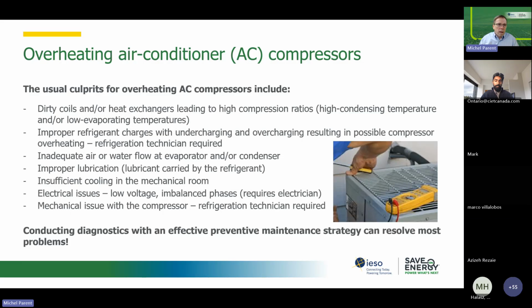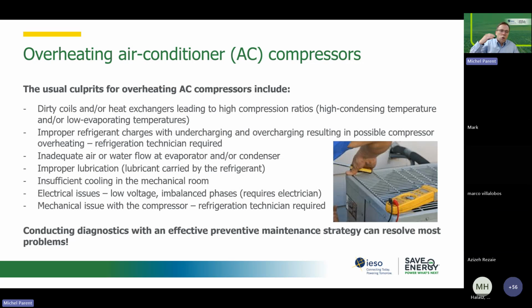If you've got ACs, air conditioners that are not a chiller, we're talking more about the type of rooftop unit and split systems. Obviously, they're motor driven. The compressor has its motor that is hermetically sealed within the compressor. Usually, the biggest culprit in failure of those is improper maintenance of the coils, besides refrigerant charge, which we'll talk about later. So you have to make sure that you minimize the lift. The lift is the difference between the evaporating temperature and the condensing temperature. If you've got improper airflow on your coils, or dirty coils, that will increase the lift. As the lift goes up, your compressor has to work harder. As it works harder, it has a tendency to overheat, and it will create failure.